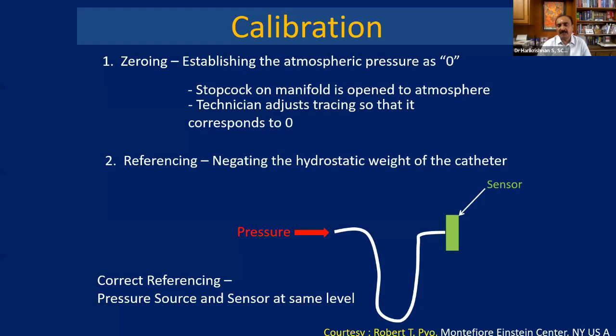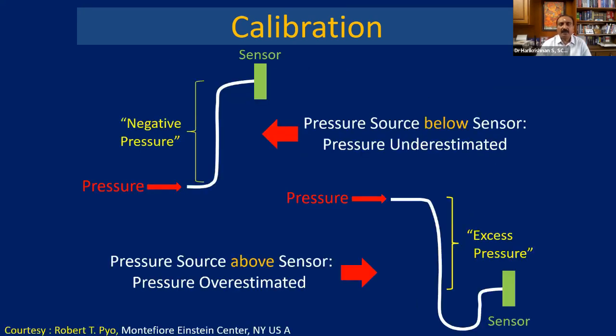Then we should know some of the terms like calibration. Calibration is the zeroing, where you should establish the atmospheric pressure reference as 0. So that is a point where you connect the pressure connector or the cable to a point in the three-way. The point where the three-way opens to the atmosphere, that is the reference point or 0 point. So once you have adjusted, never lower or raise that particular three-way, because that will change the 0. So you should not do that. Once you have calibrated, you should not change the position of the transducer. Once you fix the reference, then don't change. It will affect the calibration.